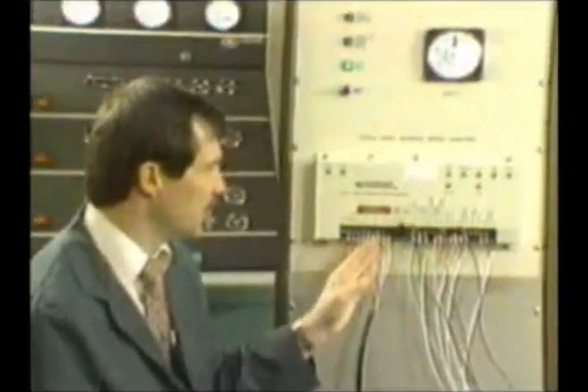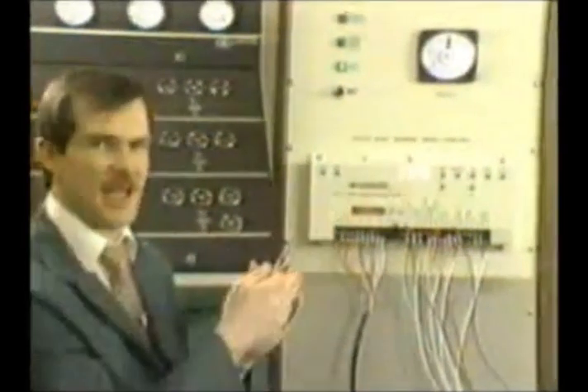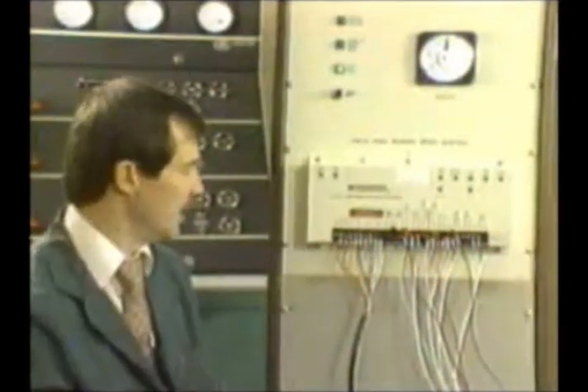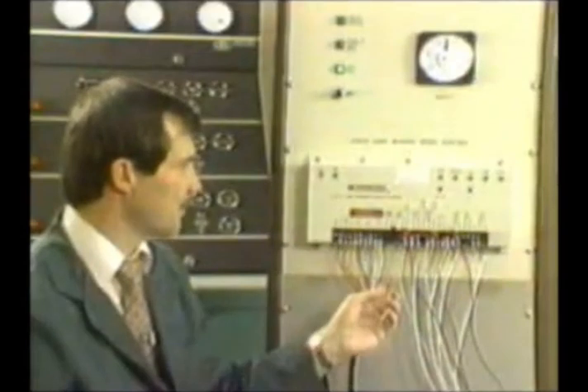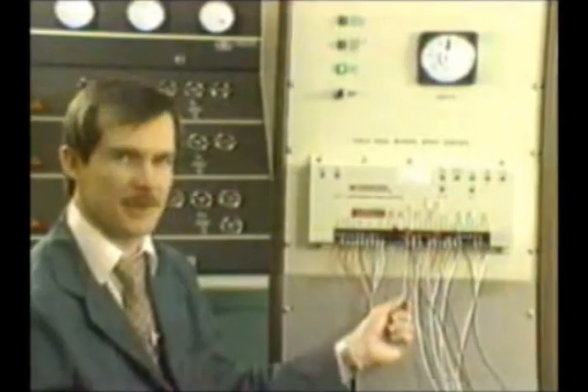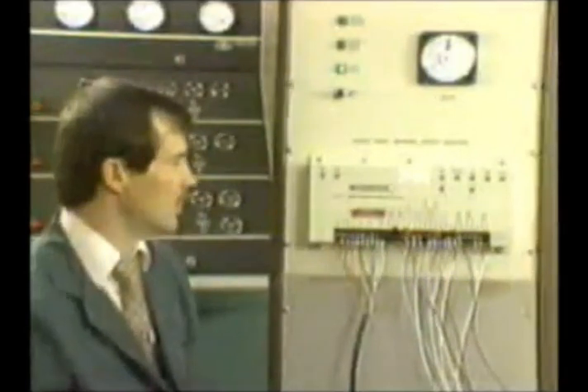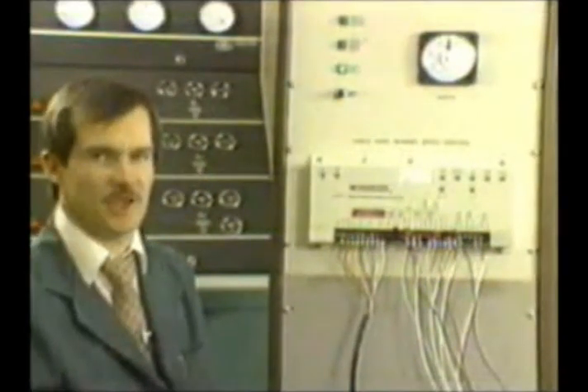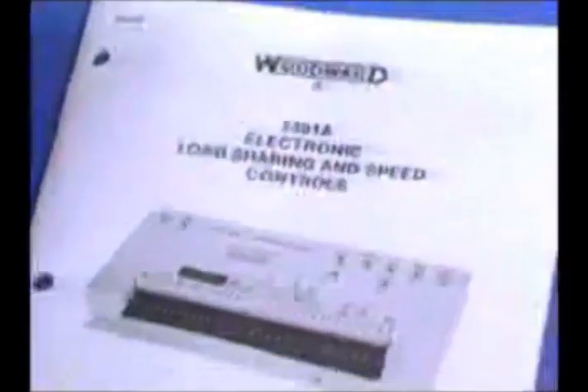Terminal 14 now, the thing I didn't show you was a contact in series with the switch. But for your application, that should be simple enough to figure out, knowing that once terminal 14 goes high, you're going to be in isochronous. And if you need to be in droop, you have to have that open. So that shows all the adjustments on a 2301A control. And if you have any questions, refer to the manual or please contact the Woodward Governor Company in Fort Collins, Colorado.